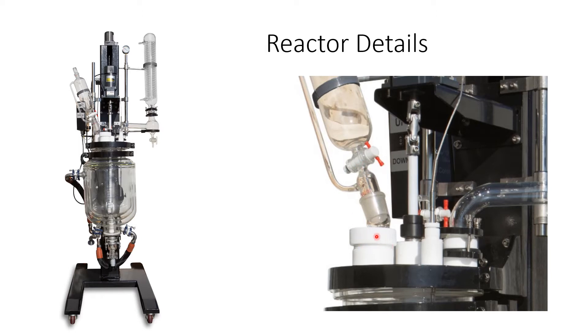This is a big material inlet port — basically you could unscrew this cap and add stuff to it. This is a stir, which connects to a big overhead stir right here, so you could stir up some pretty viscous samples. This is a thermocouple right here, which measures the temperature of your inner contents. This one in the back is an inlet valve — if you wanted to pull vacuum or add something to your system, you could use this one. It connects over to your reflux condenser.